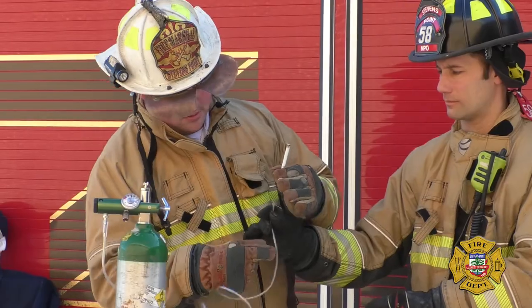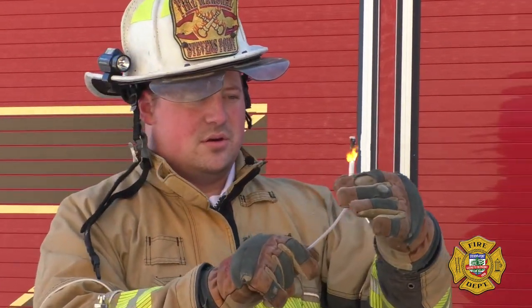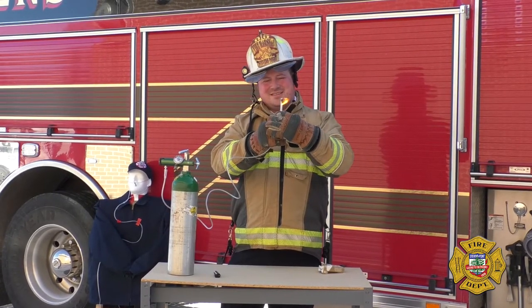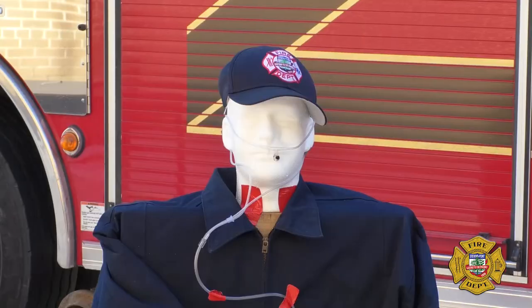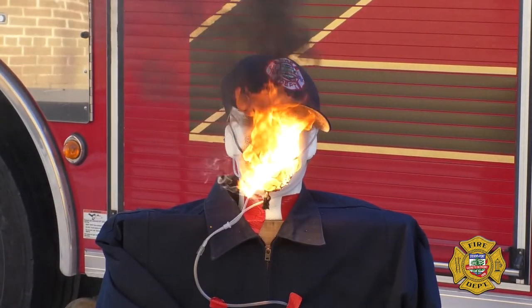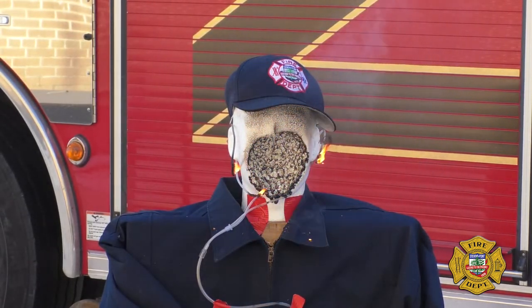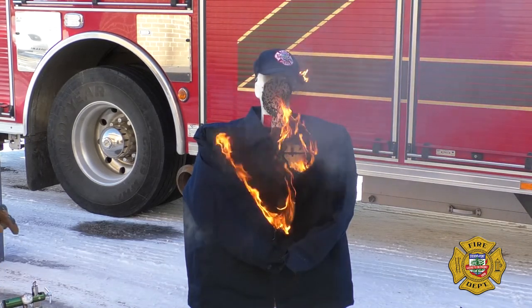Now with the oxygen flowing, you can see the cigarette rapidly oxidizes and combusts until the oxygen is removed. As soon as the oxygen is removed, that cigarette either goes out or returns to a normal burning phase. With cigarettes and oxygen sources close to our face, we're going to get high-severity injuries because of that rapid burning. Oxygen, when used near your face where it's typically applied, can saturate your hair, clothes, and the surrounding area with a higher oxygen concentration — increasing the flammability of clothes, hair, accessories, and furniture, causing severe injuries.